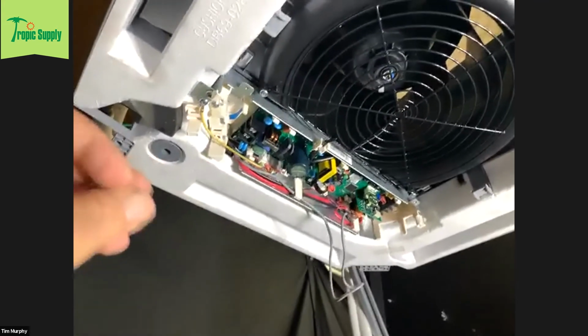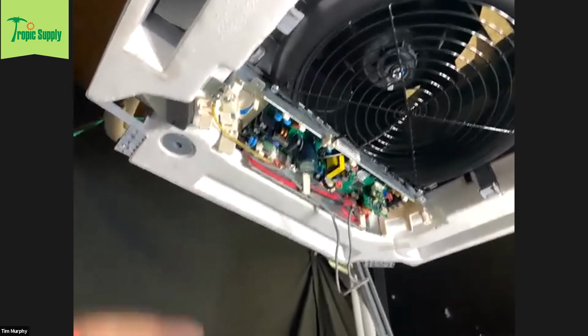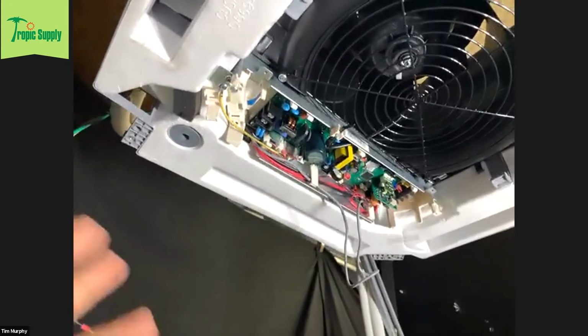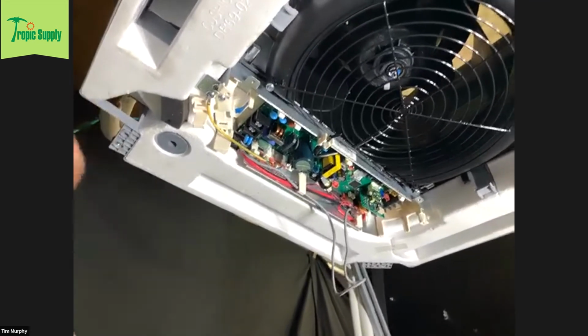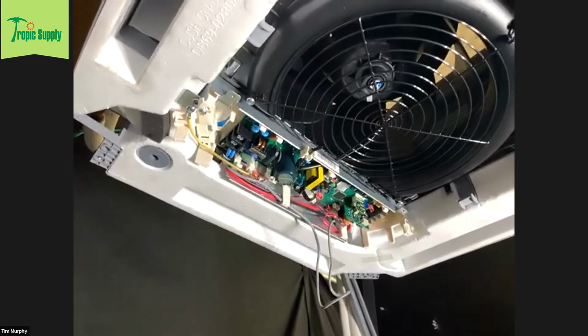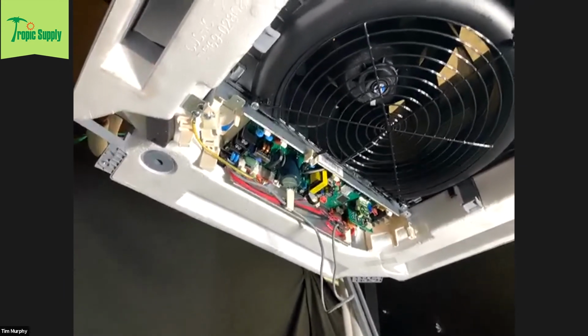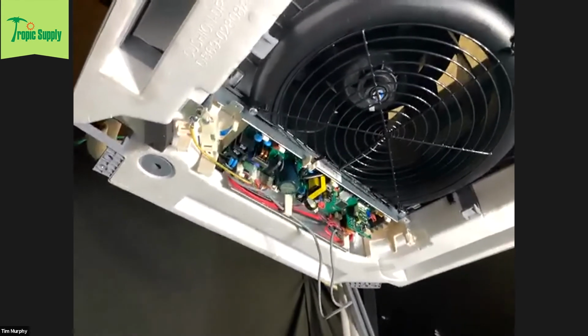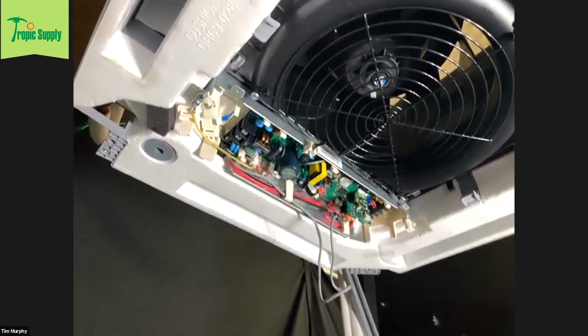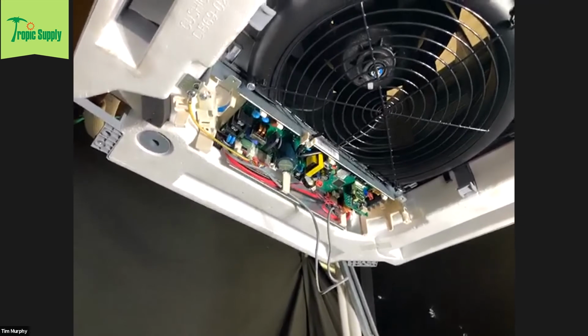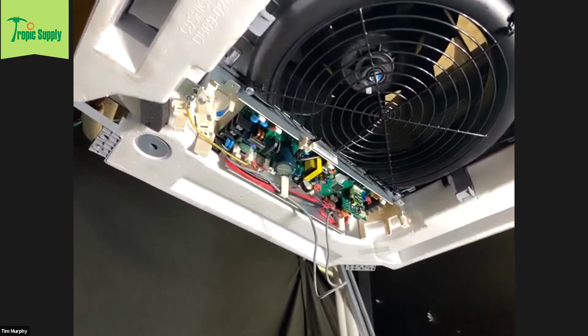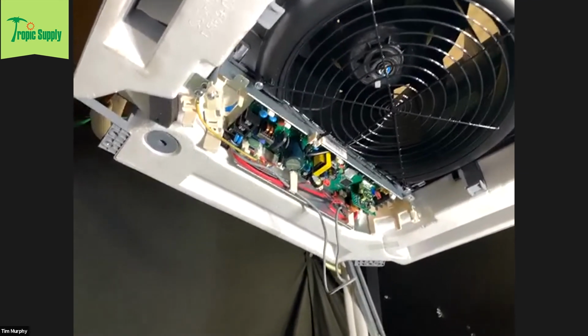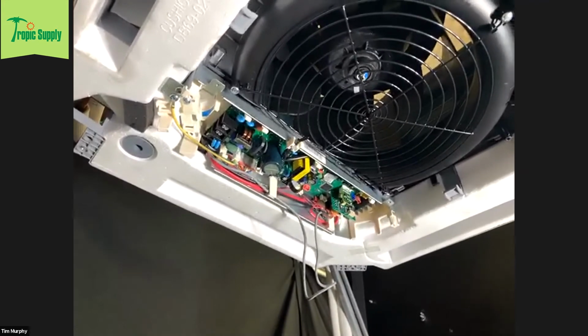So if you open the installation manual, you don't call technical support and say, oh, well, it says in the manual you can extend the control wire. No, you cannot. The communication wire or control wire, or whatever you want to call it, needs to be one continuous wire from the outside unit to the inside unit, whatever inside units you're running. And the 16-2 shielded wire is what is recommended.